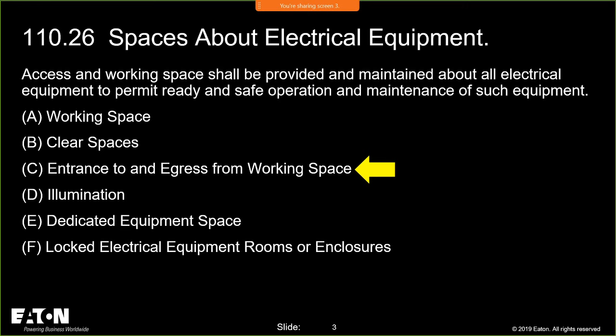Even if you've not adopted the 2022 code yet, my advice to design engineers is take your next design where you have equipment 1200 amps and above, or where the handles are all added up to 1200 amps and above. We'll talk about that a little bit more. Make sure you consider this in your design and see how you may have to change your design, or you may have to go back to the architect and say, I need more room. But they modified C, entrance to and egress from, and this is basically the change in large equipment.